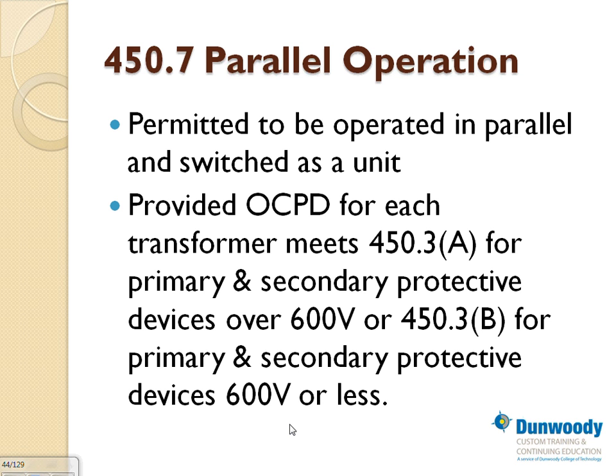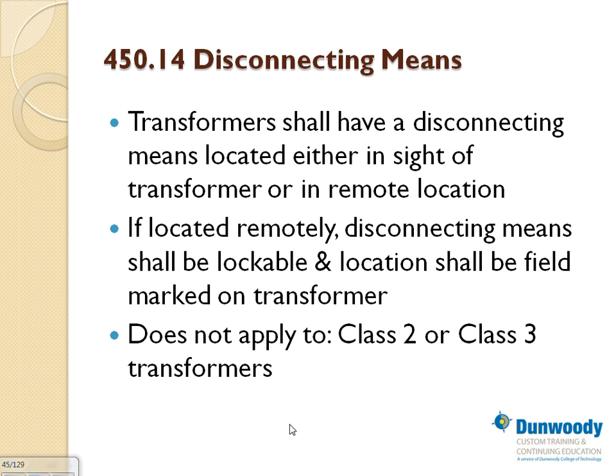Paralleling operation: can I parallel two transformers to give me more power? Yeah, we do it all the time. They're permitted to be operated in parallel and switched as a unit. Overcurrent protection: if you do it this way, for primary and secondary protective devices over 600 volts, it is based on this table. So you have to have an overcurrent protection device based on the table. But can I tie two transformers together, phase A, B, C, and run the whole building with it? Yeah, they use it. Utilities use it all the time to get you more power, but make sure you have an overcurrent protection device for them. You can operate them, but you have to size the overcurrent protection device separately for each one of them.